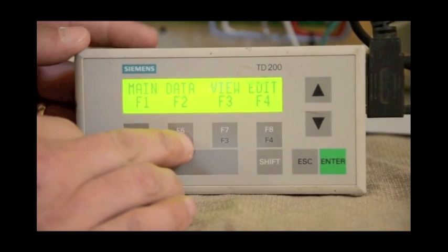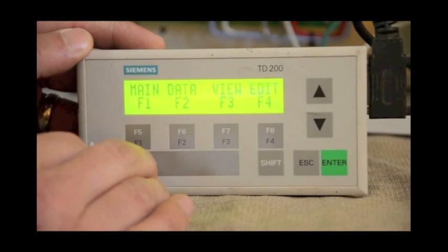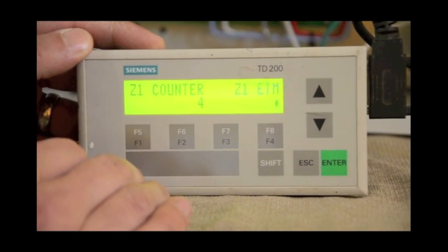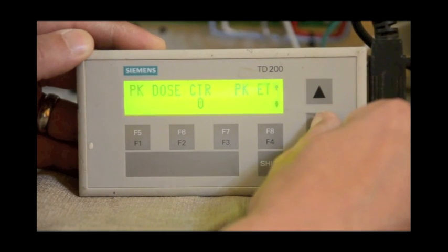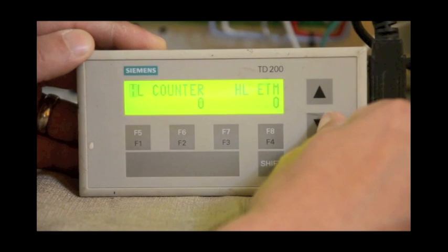The first screen we're going to talk about is F2, which gives you access to all of your data logs and cycle counters. Simply press the F2 button, you'll see zone counters and zone ETMs for each one of the zones. You'll see the same counters and elapsed time meters for the pumps, for peak, and for high level. The last counter records the number of field flushes per zone.